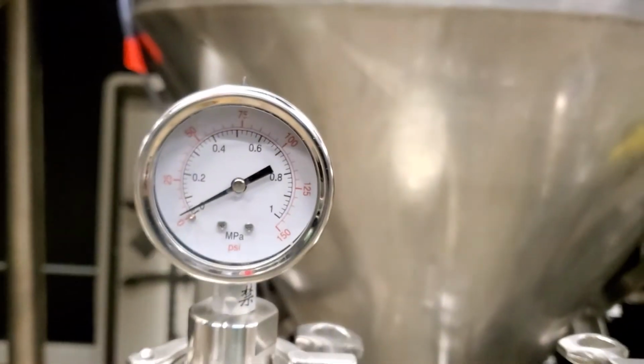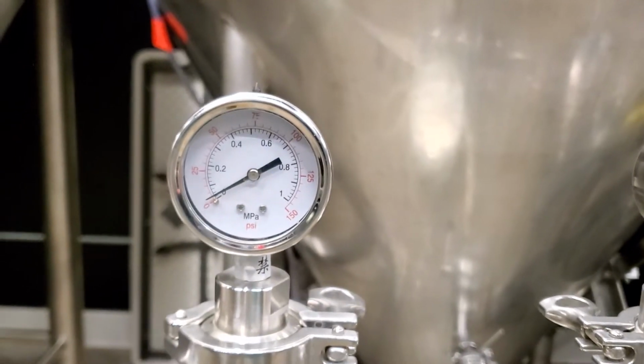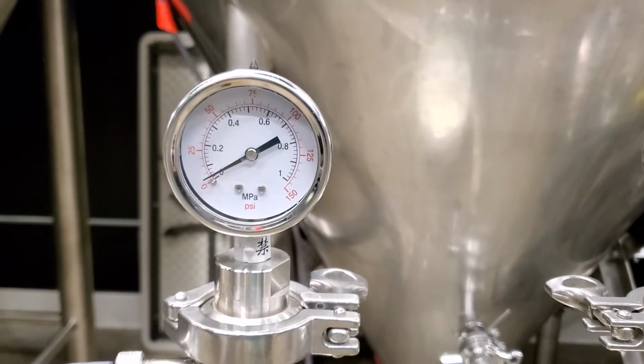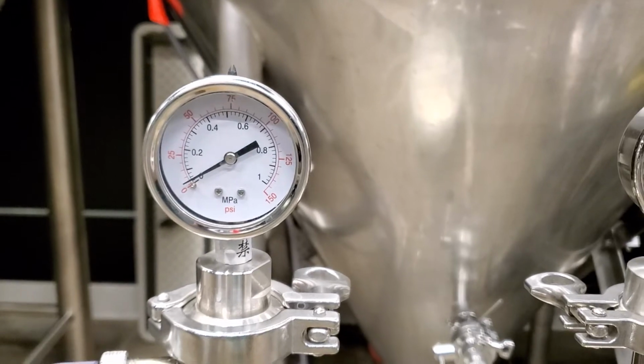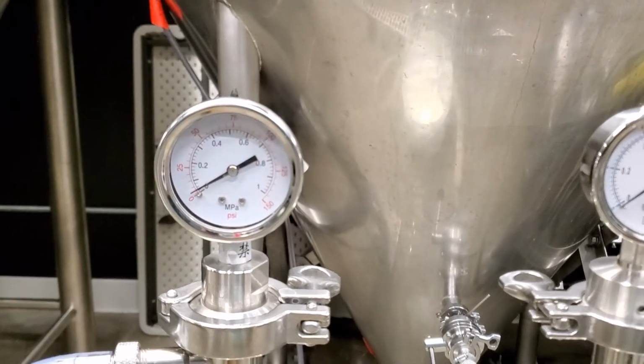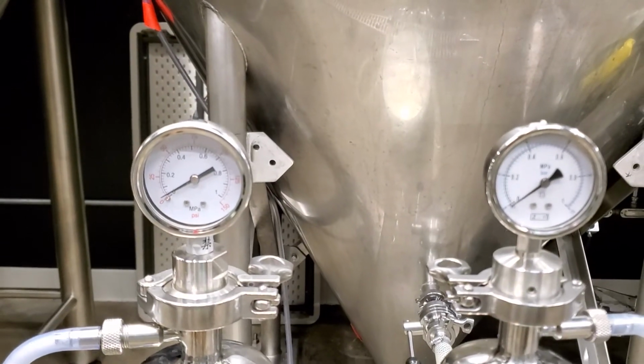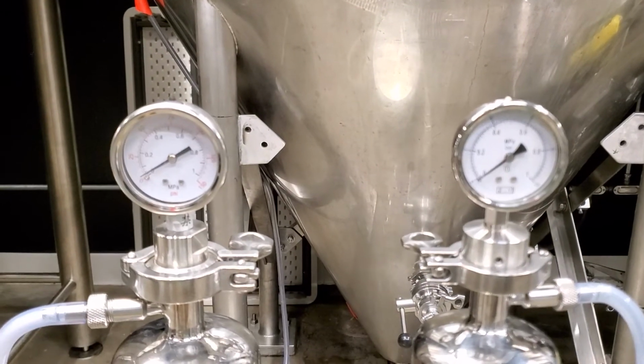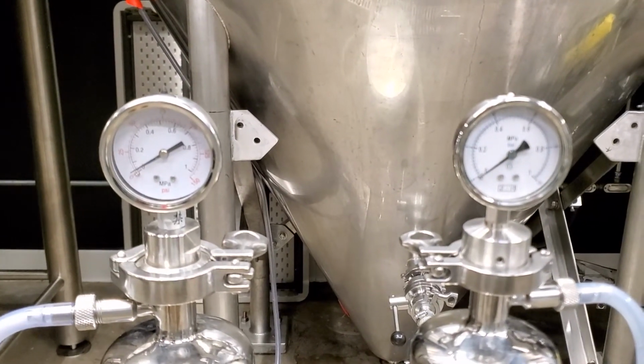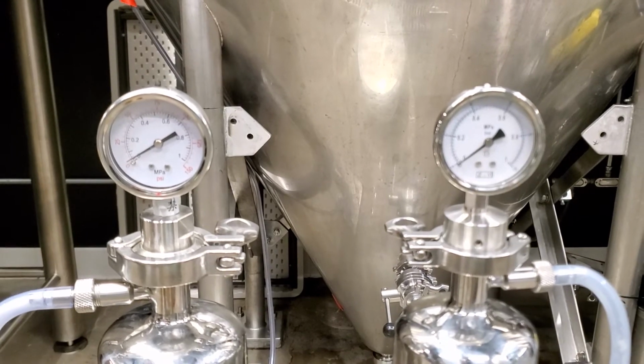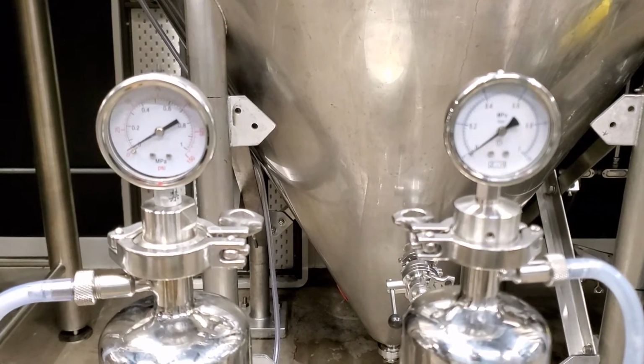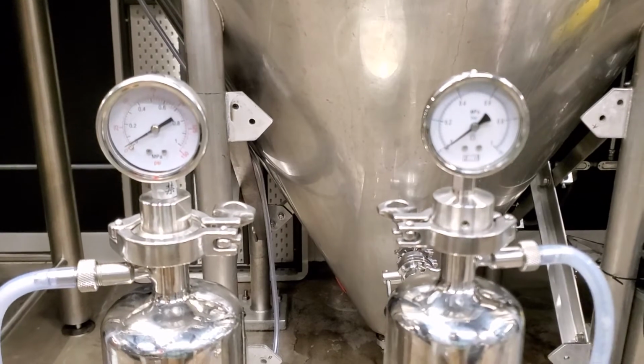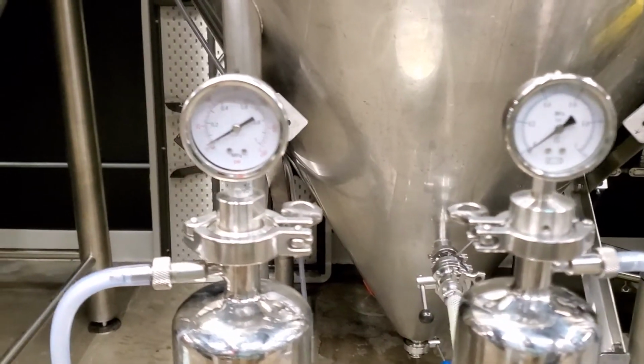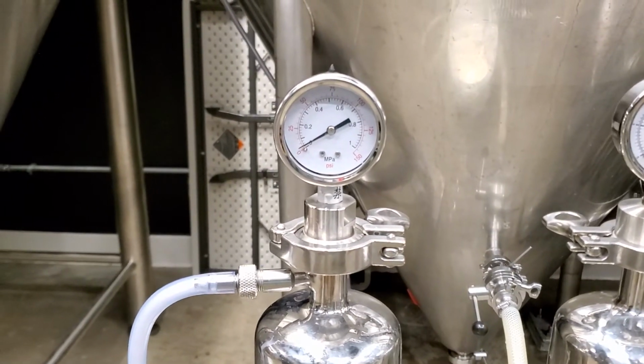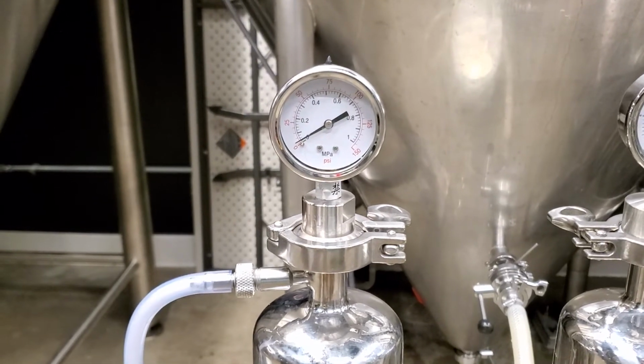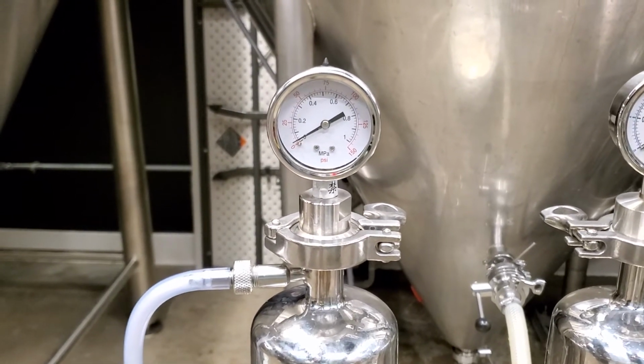We're going to watch this pressure, check it out every few minutes or so. We really want to make sure that this 0.45 cartridge does not get clogged. It's a very expensive filter, about $350 each. And if we can save it, if we can regenerate it with a little bit of sodium hydroxide solution and citric acid to neutralize, then we'll do that. It's better to save a couple hundred dollars by spending a few hours running a regeneration on this.